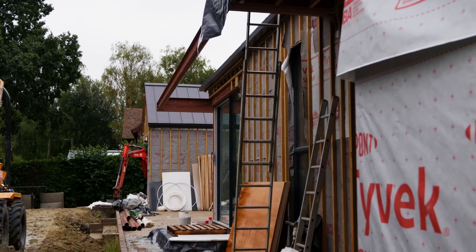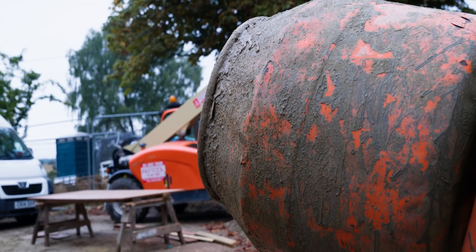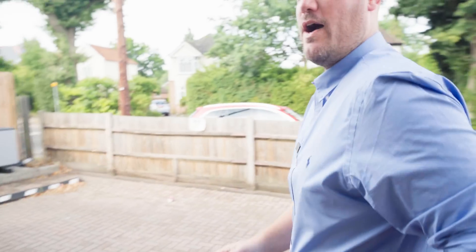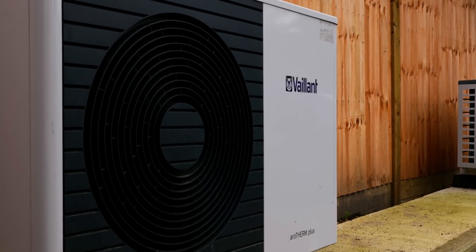Ordinarily, we've got an electric boiler on a jig that we set up for that, but it's going to be used on another project. So thinking outside the box — we can't get them an air source from a normal merchant, so we've got one of our own. This is our Aerotherm Plus — we use it to heat our office. It's August at the moment, we're not using it for heat, and our hot water is done by solar thermal. So we're going to take this, go and fit it in the customer's house, put some controls on it, put a wiring centre on it, plumb it in temporarily, and give them the heat they need.